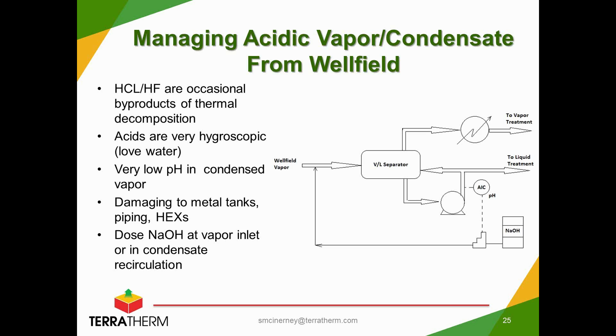And the issue is that those generated acids may be coming out in a vapor into our header. Our well field vapors, as I pointed out earlier, are often at 100% saturation. We start to condense water in our vapor piping. And so a little bit of water and a bit of acid. The acids are very hygroscopic. They're loving water, and that translates to potentially very low pH water entering the head of our equipment. And again, that's quite damaging to metallic treatment components.